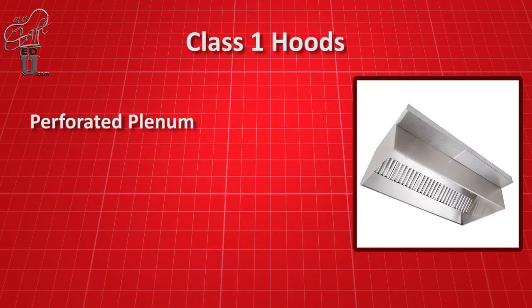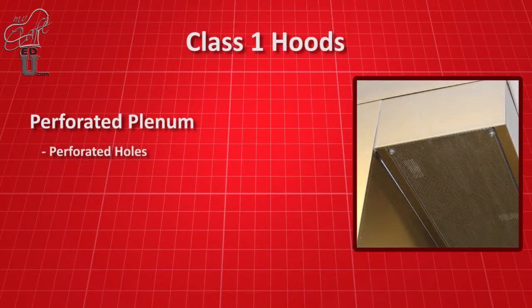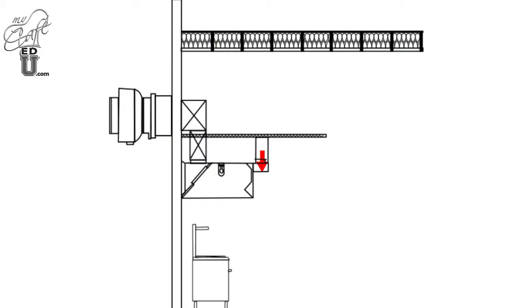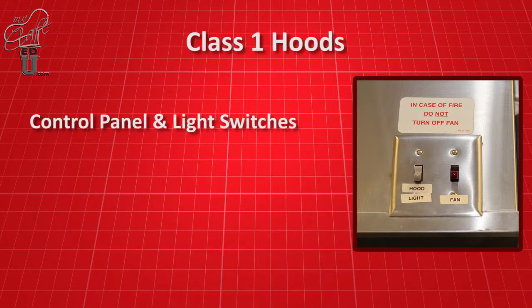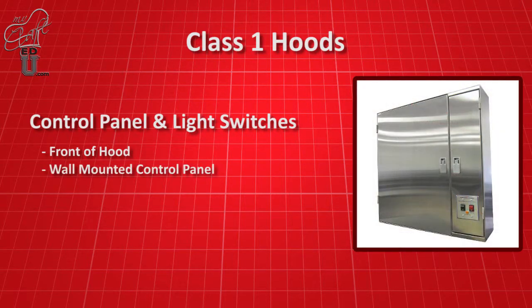The plenum runs the length of the hood and is located on the front exterior of the hood. Plenums feature perforated holes the entire length of the plenum to allow for a gentle down discharge of the incoming air. The air flows down the face of the hood and is where a large percentage is recaptured by the exhaust fan, pulling it back into the hood and out the exhaust duct to complete the cycle of airflow. Control panels and light switches for Class 1 exhaust hoods and fans are typically located on the front of the hood for easy access or in a wall-mounted control panel.